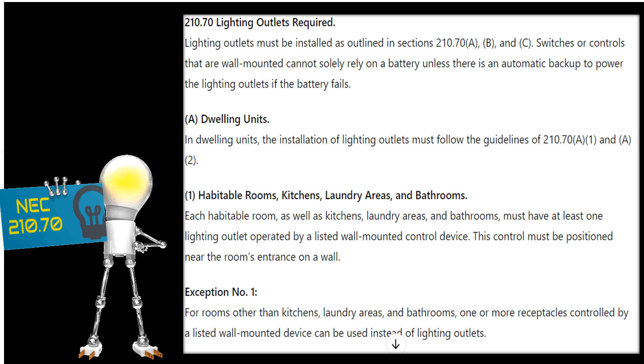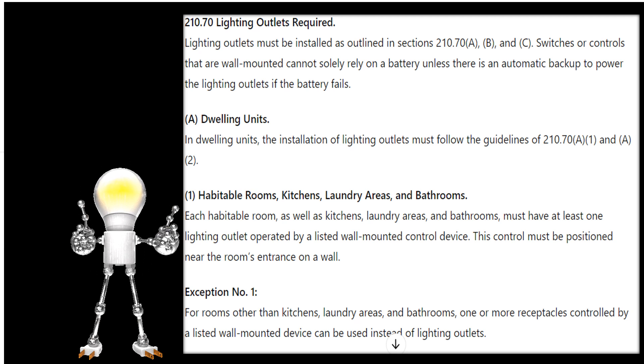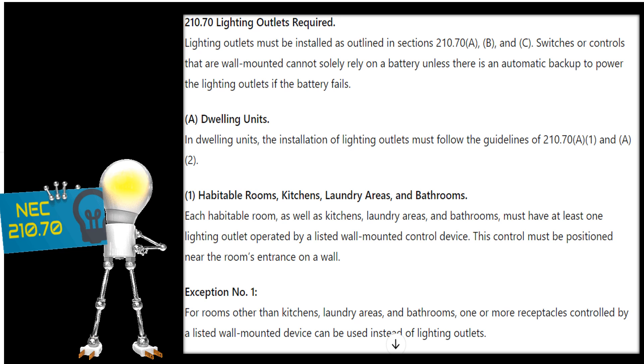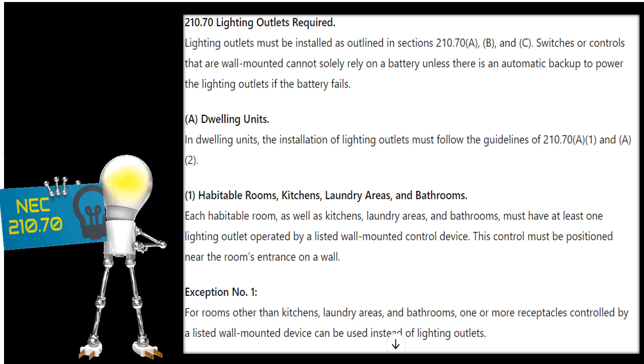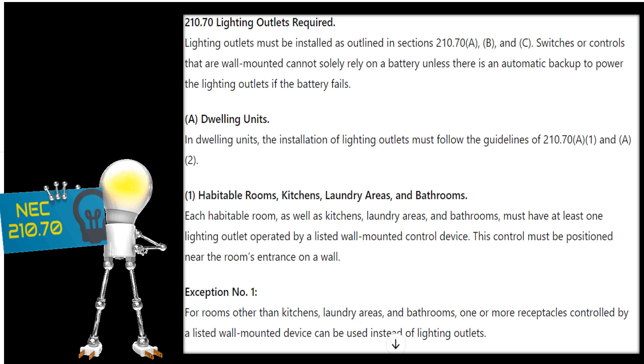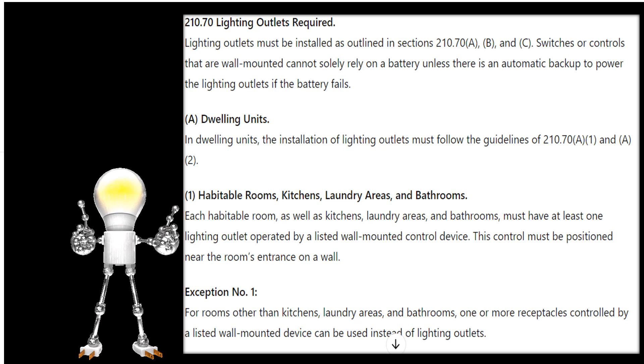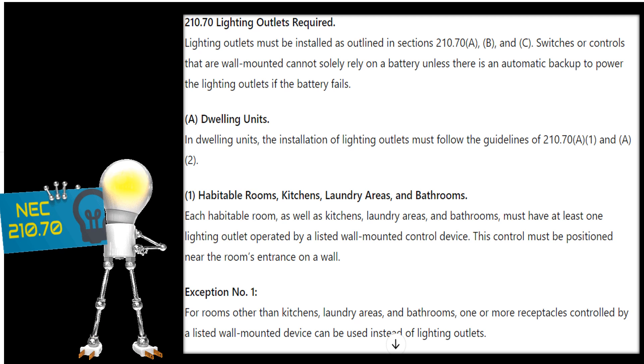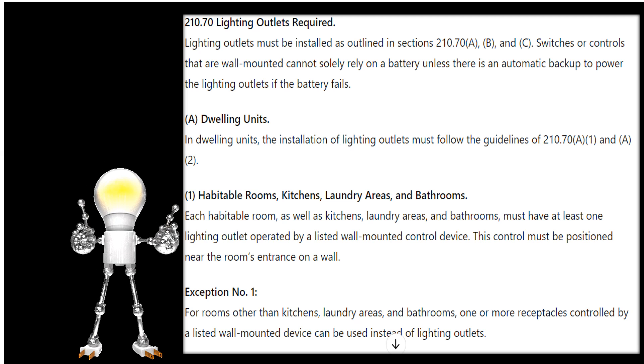In kitchens, laundry areas, and bathrooms, you must have a physical lighting outlet. It doesn't dictate that it has to be on the ceiling — it could technically be on the wall as a wall sconce. It doesn't specify height or anything like that; it just says you have to have a true traditional lighting outlet in kitchens, laundry areas, and bathrooms. In the other areas required by Part 1, you're allowed to use a switch-controlled receptacle, and that's perfectly okay.